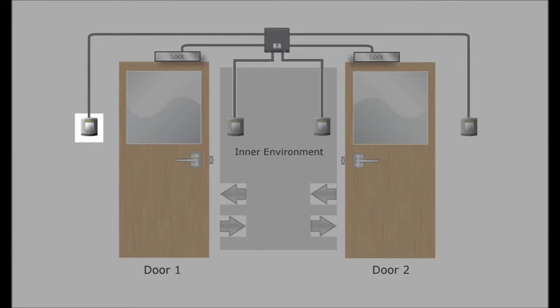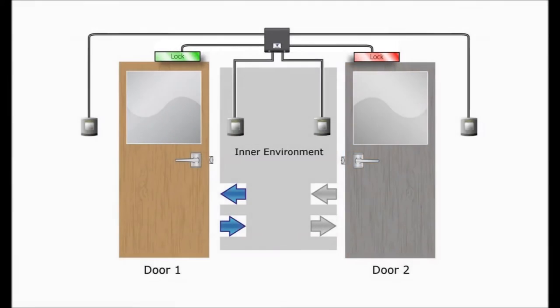The system follows the sequence: first of all, to request to open a door. The switch on the contact for door one is closed. The system reads the status of door two and understands that it is in the closed position, and will accept the door request and energize the lock-out relay. Door one is now accessible.